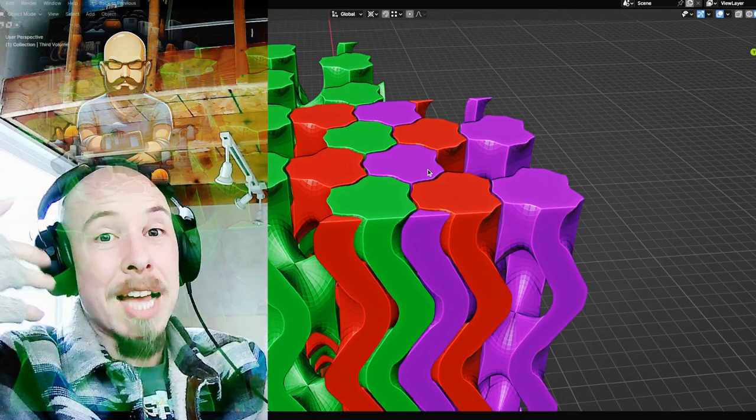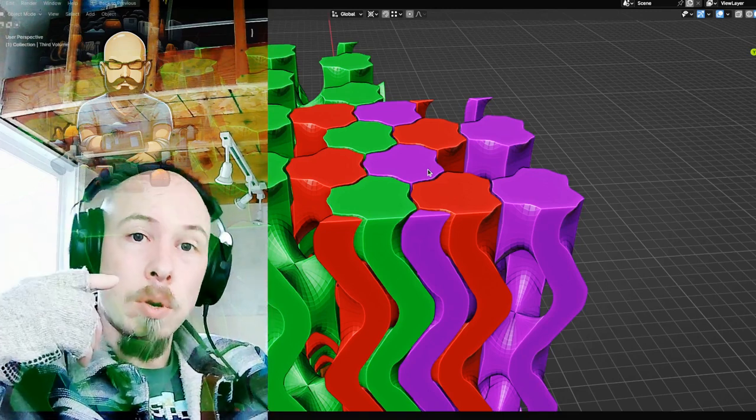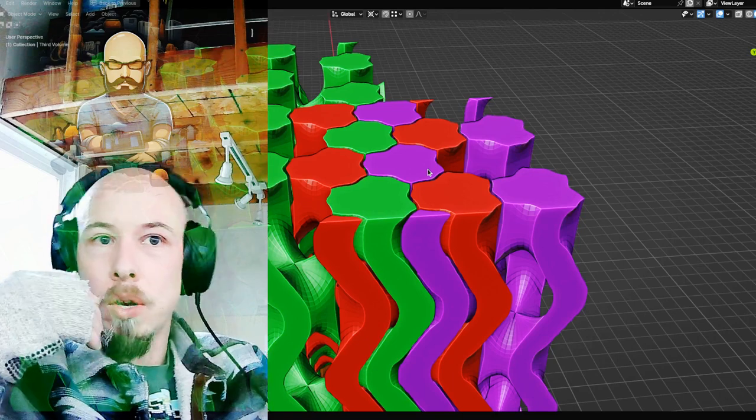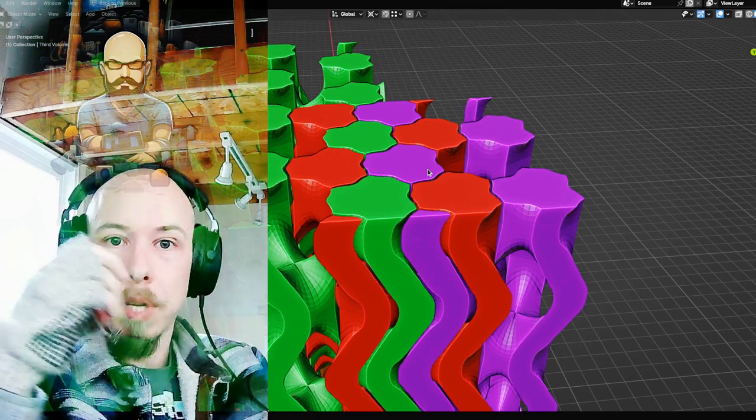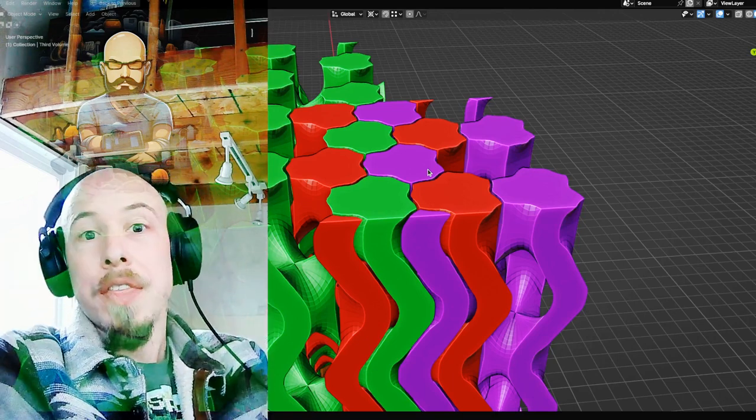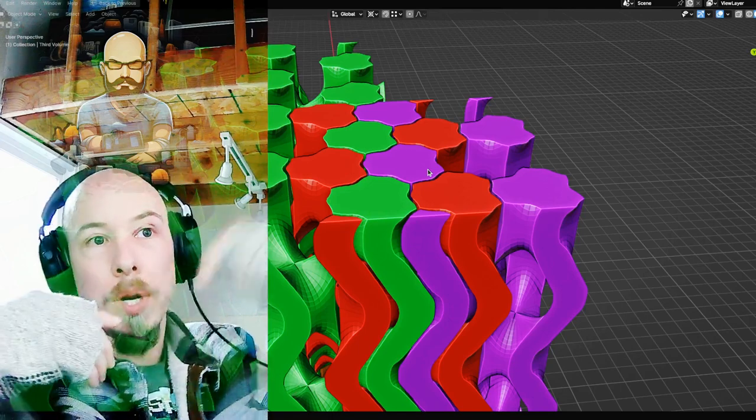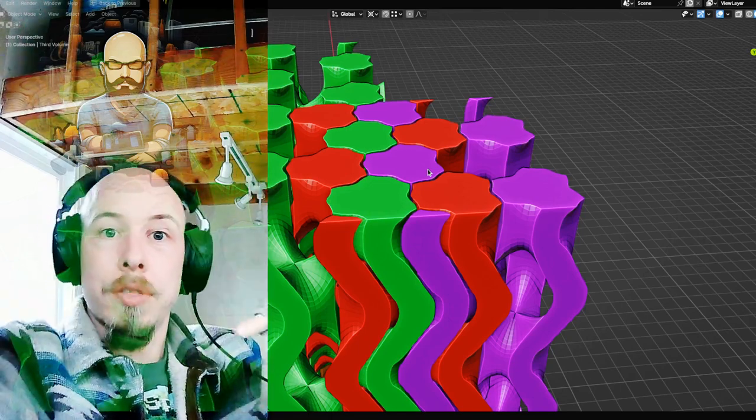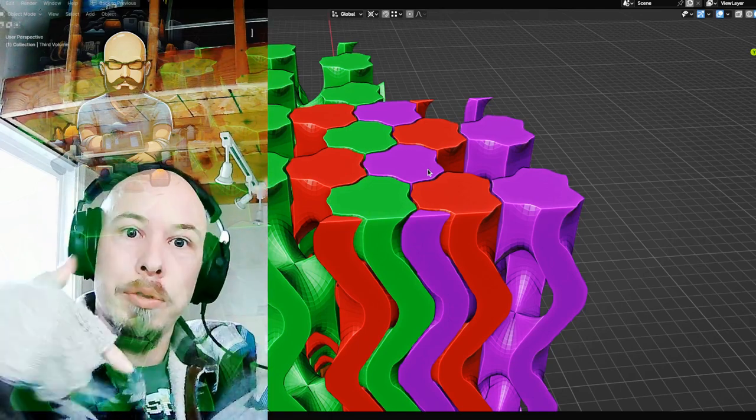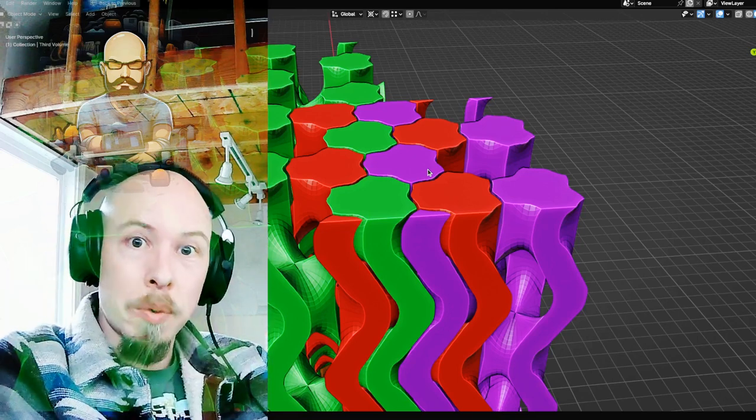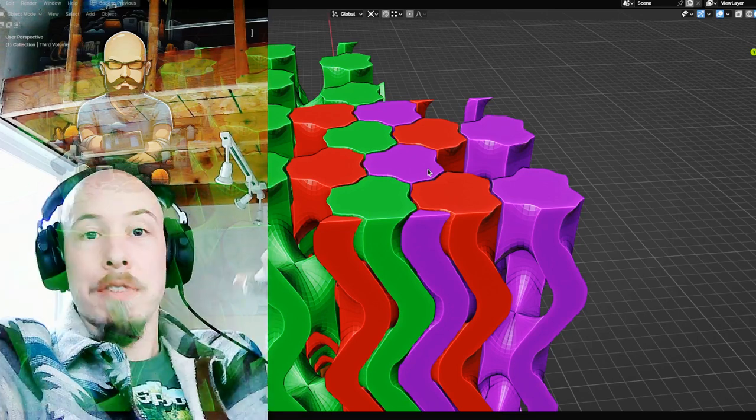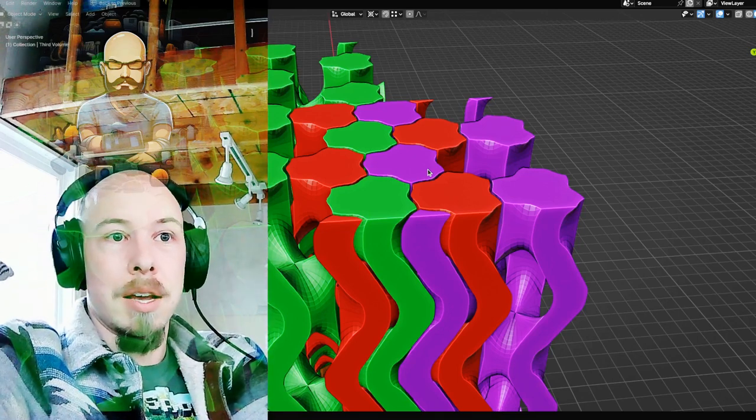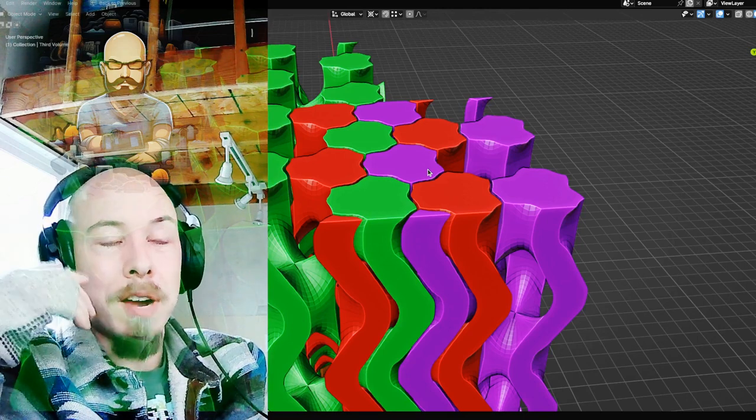It's not going to be as efficient, but it'll be pretty efficient. And then you can run a clean fluid or purge or whatever you need to do to clean out that third volume. Then you can convert that one back over to a process fluid and clean the other two volumes in that way. So you can cycle through all three volumes, clean the whole thing without ever taking it out of production and without ever taking the thing, disconnecting it from the factory or whatever.